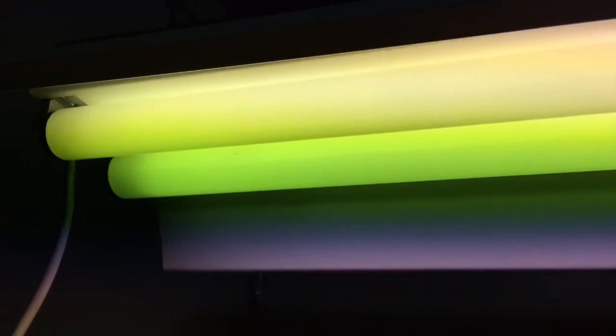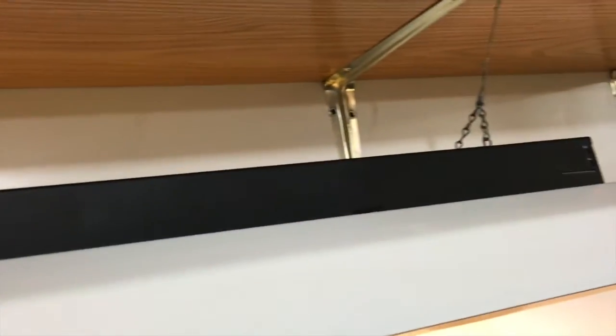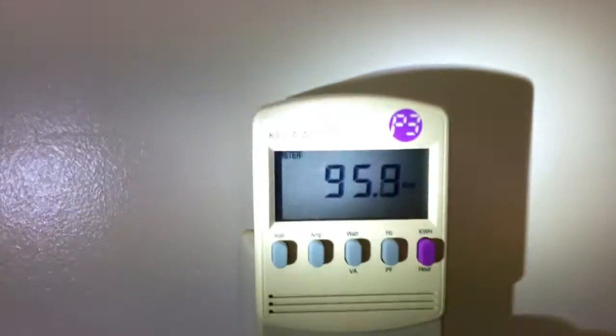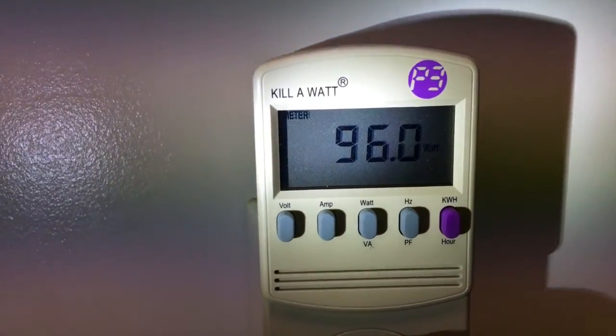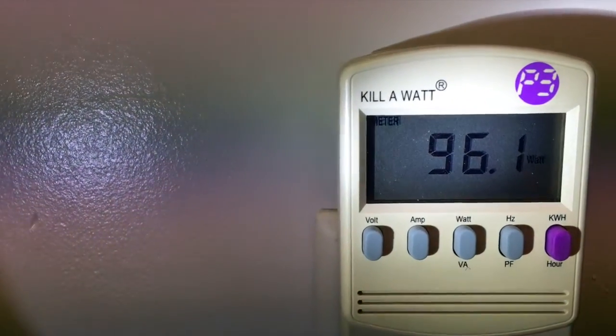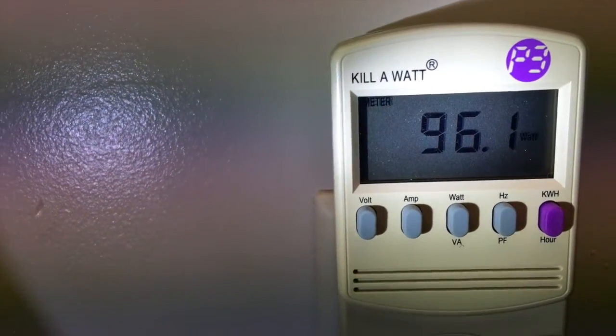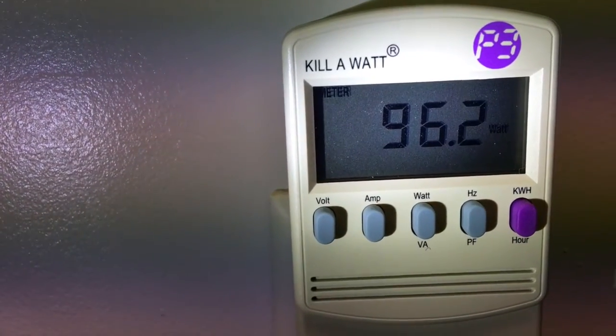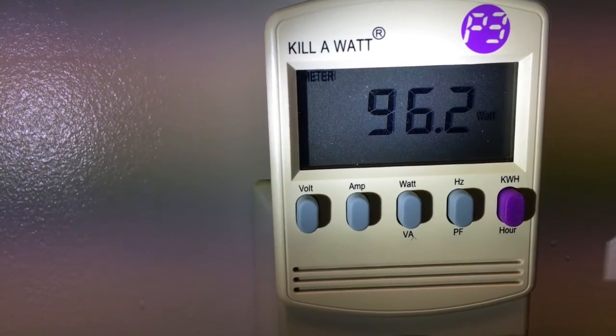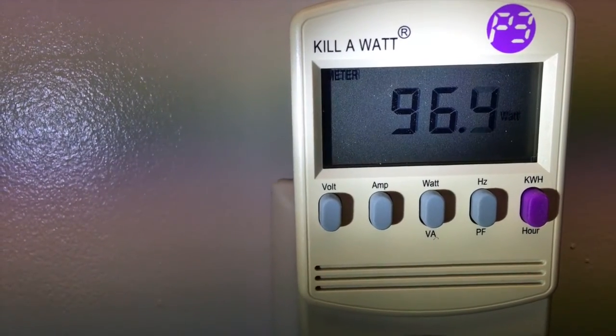And above my workbench, I have the traditional fluorescent tubes, the same fixture, same ballast that was in it, same light about the same time. I just painted this one black to give it a little bit different look over here. Four foot fluorescent tubes, and of course these are the 40 watt tubes. So let's come down and check out what we're using for wattage. Right there you're seeing, I'm going to turn the light just a little bit more. So we were using just under 38 over there, and now with the fluorescent we're using 96, a little over 96 watts.